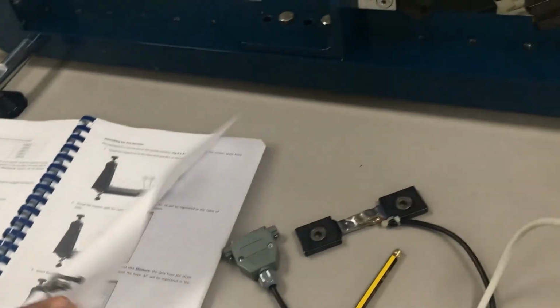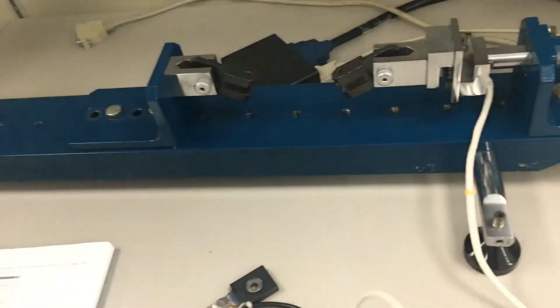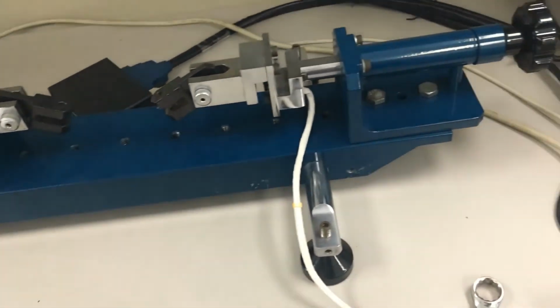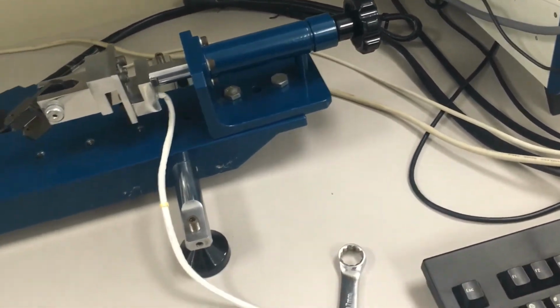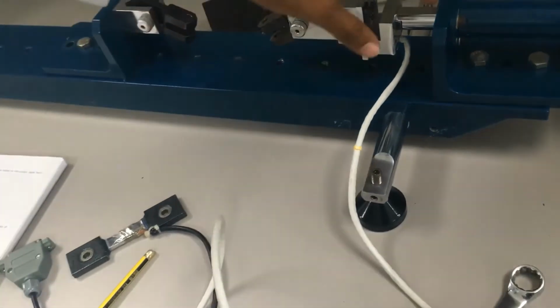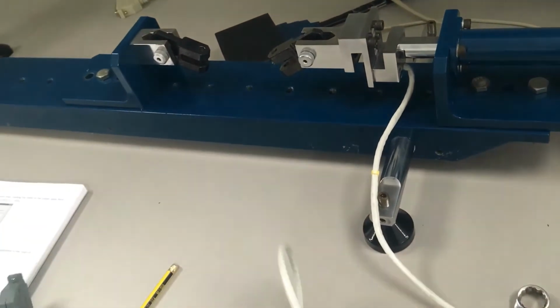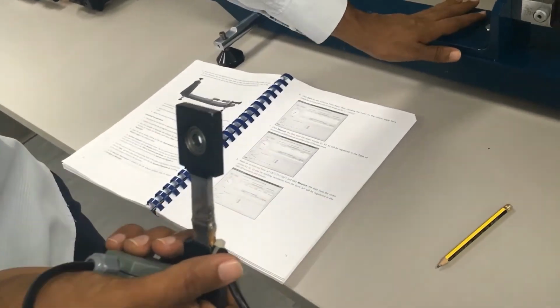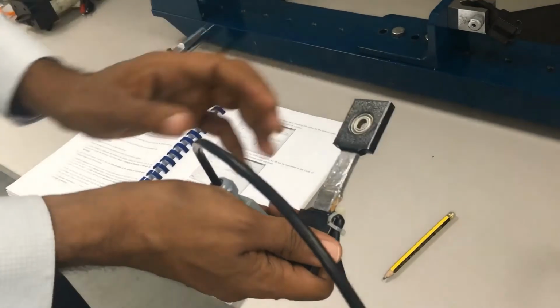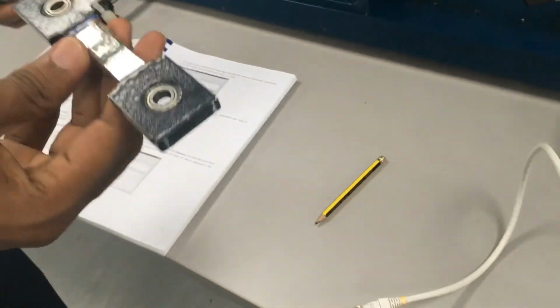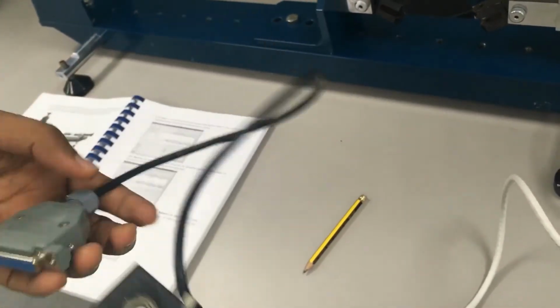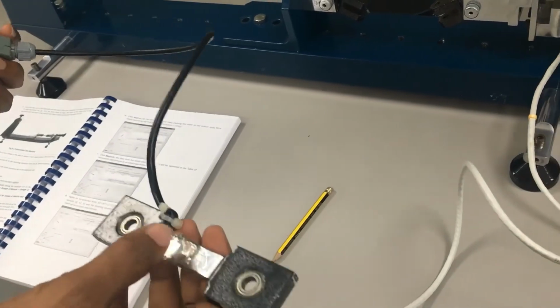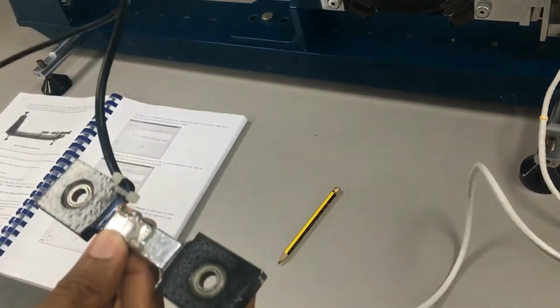Perfect. Last step, we need to insert the specimen number 1. So as you know, we have two tables, table of materials and then another table of specimens. So this is specimen number 1, not to confuse with the element number 1, which is the support. So that was an element and this is a specimen. A specimen is anything that has sensors, and this cable for reading data through sensors. So this is the last thing.